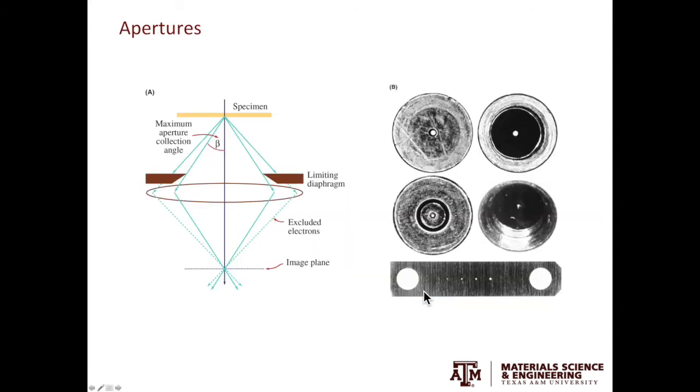Moving from lenses to apertures, apertures are much easier. These are just small holes in diaphragms. The aim of having apertures is to limit the angular spread of electrons entering the lens. In the example here, the electrons with scattering semi-angle less than beta will go through the lens, but the electrons with scattering semi-angle greater than beta will be blocked by the aperture.